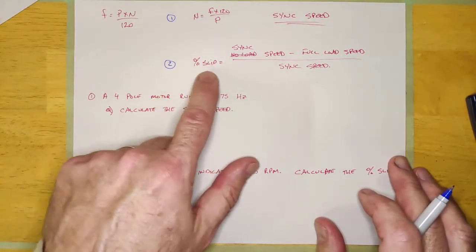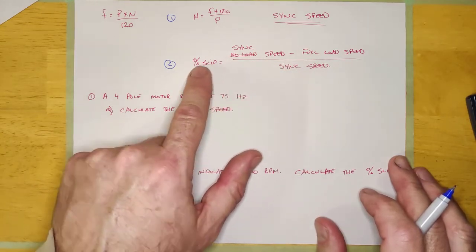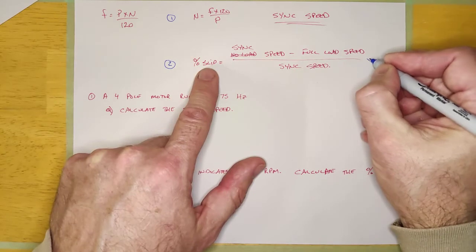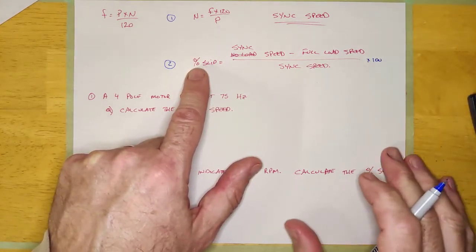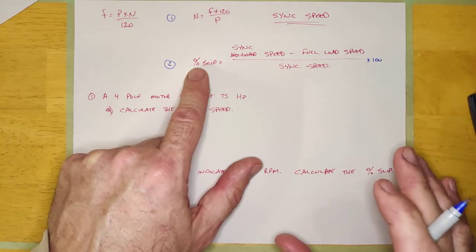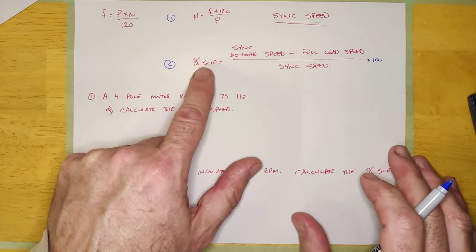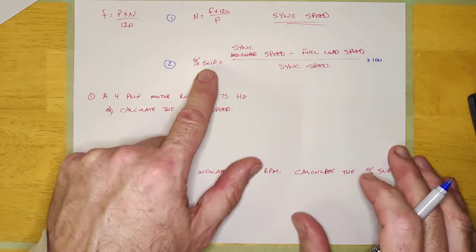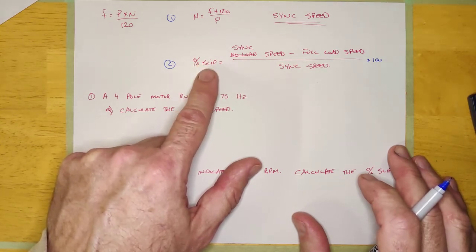The other formula that I want to talk about really quickly is calculating the percent slip. And what the percent slip really is, is how much is it slipping? How much is it slipping from no load to full load, essentially. So the lower the percent slip for a particular motor, the less it's slipping or the less of its sync speed it's slipping. And so the lower the percent slip, kind of the better the speed regulation of the motor.